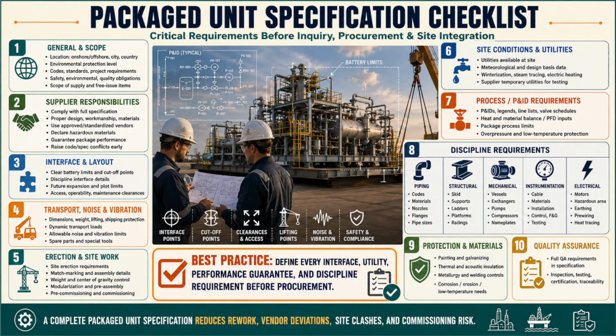Provide voltage levels, frequency, system fault levels where applicable, and the intended use of each supply. Define control voltage, heater supply, lighting supply, and emergency power requirements. Avoid duplicating specifications, because duplicated requirements frequently conflict. Where the package deviates from a general project specification, state the variation explicitly. Include electrical heat tracing and cable requirements where applicable.